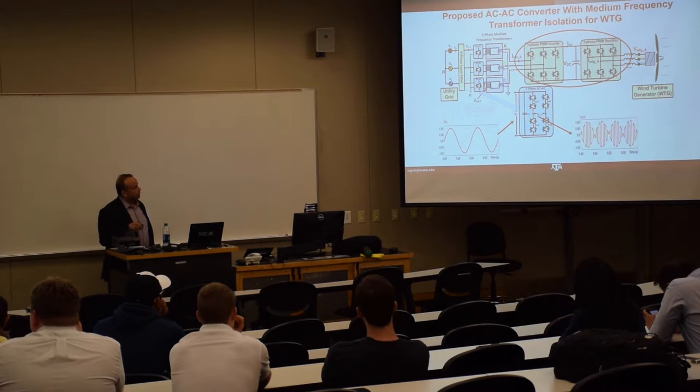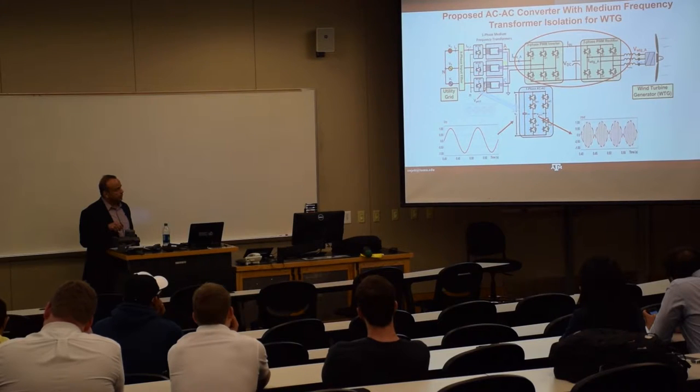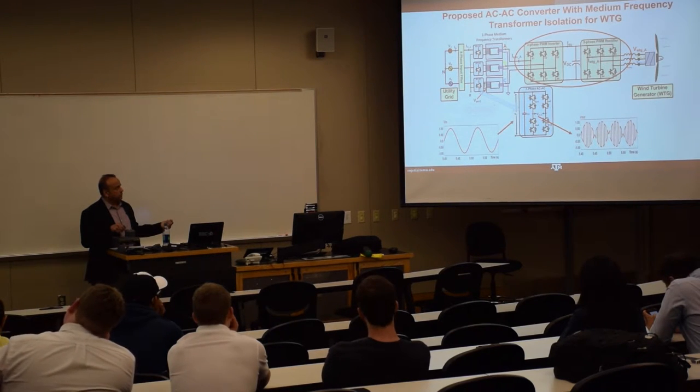Now on the secondary side, you notice that I'm not really making a sine wave. The solid state transformer folks make sine waves because they want to apply their solid state transformer everywhere the regular transformer is. Whereas my focus has been that you eliminate the secondary converter based on what the application is. In this case, we have eliminated the secondary converter and kept the primary converter the same as before. Now all we have to do is change the algorithm on this converter so that when the voltage appears across these terminals like that, the current also has to be the same shape. So I have to emulate a resistance here continuously in a negative way, because negative means the power is going back. That's what this converter has been modified to do, modifying the control algorithm.